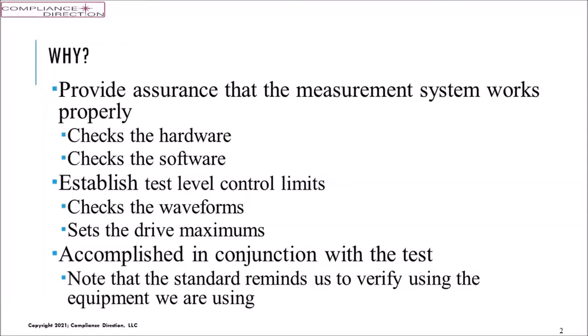Now, as with any verification, the depth of how good it is depends on how well you've set up your procedures and your controls. But if we follow the steps and the various things that we'll be discussing, we tend to get a good level of verification. We also use the pre-cal or pre-test calibration work to check test levels and control limits for the susceptibility waveforms and test levels. We normally check the waveform parameters and we set the drive level maximums, or those that we'll be using for the test, depending on which type of test it is.